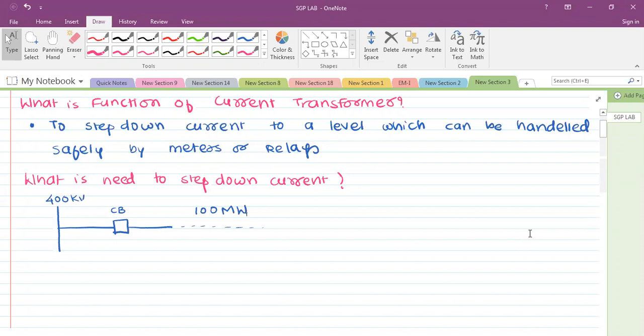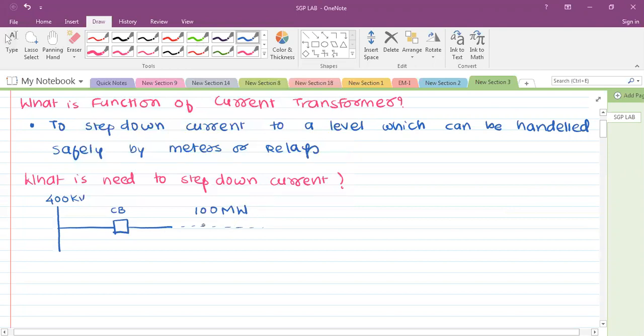So it is 100 megawatt upon root 3 into 400 kV, which comes around 250 by 1.73, about 144 ampere - not kilo ampere, 144 ampere. So this current will be the rated current. Let us assume that 100 megawatt is the rated capacity - it is actually much more than this for a 400 kV line, but we are just considering this for understanding. So the current in the line here will be 144 ampere.